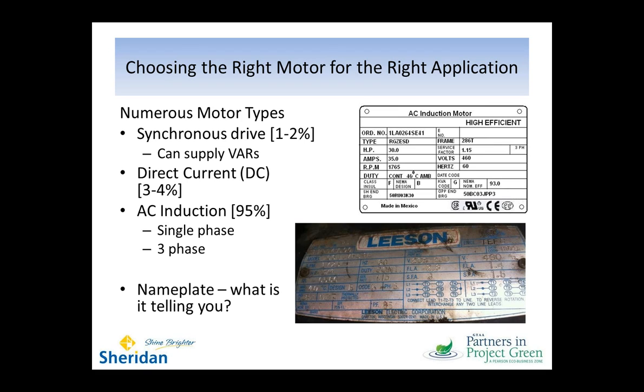We also see things like class. There's one called NEMA design. Those go A, B, C, D. They tell you about the torque characteristics of the motor. You see at the top right a frame designation, 286T in this case, which tells you about the bracket and bracket hole locations and all of the physical size and specification of the motor. These are all standardized. So you could replace a 286T frame motor with a 286T frame motor, and you're guaranteed you'll have the mechanical fit. So lots of good information on there for you.